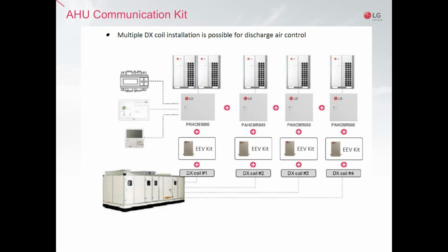In the case of the return air control, there is no limitation on the number of EEV kits. So even though we cannot use the 594 size, we can have more than 4 EEV kits connected to the same air handler unit, giving us a very large potential of capacity for these units.